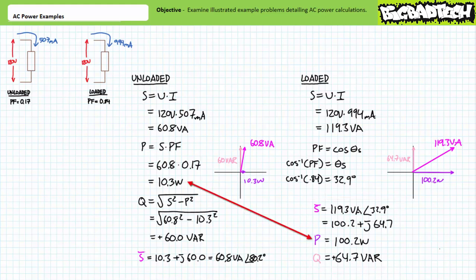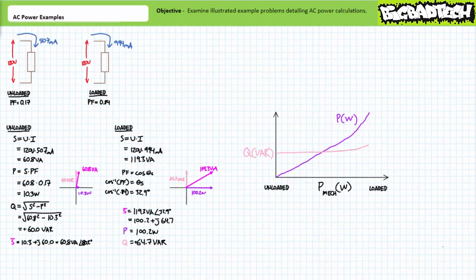As we anticipated, real power in the loaded condition is much larger, almost 10 times larger than in the unloaded condition, meaning a larger proportion of apparent power is now directed towards actual work. Note, however, the motor still consumes a measurable amount of reactive power in the loaded condition. In fact, despite a dramatic increase in real power consumption, reactive power consumption remained relatively constant, increasing only slightly. This is a classic characteristic of induction motors.